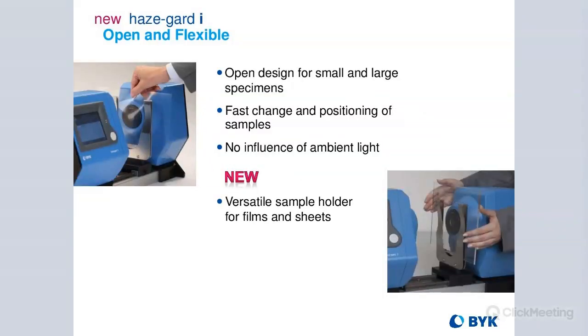The haze-gard i is open and flexible. It has an open design for small and large specimens, which makes it much easier to use than some competitive instruments that require closed optics and a cover over the whole thing. With those, you have to set your sample in place and then set the cover in place, which takes a lot longer. The open design is very convenient for taking measurements quickly. There's no influence of ambient light, and there's a versatile sample holder for films and sheets.